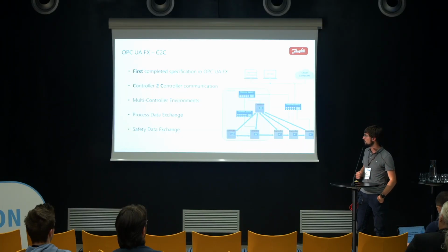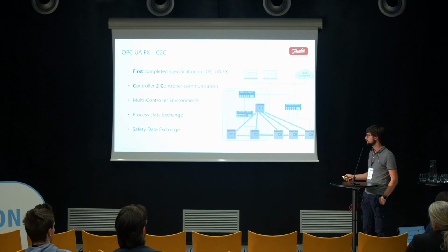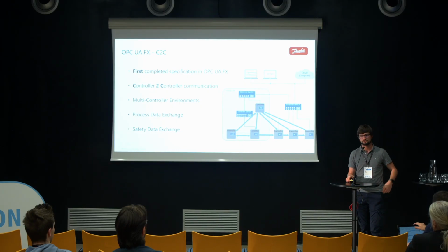We know exactly when our data arrives, and we know exactly when we can send the data, and the other device, the drive, sensor, whatever, knows when it can expect new data, which then allows it to interpolate and handle things more deterministically. The controller-to-controller specification now also includes safety data exchange specifications. There is process data and there is safety data.